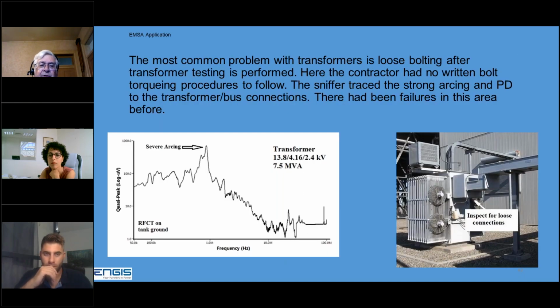The most common problem with transformers is loose bolting after you do a Doble test on the transformer. At this particular site in Wyoming, the contractor had no written bolt torque procedures to follow. The sniffer traced the strong arcing that we saw here, again around 1 megahertz, to the connections for the non-seg bus going into the side of the transformer. This is where the arcing was taking place. And when we told them that, they said, well, we've had failures there before. Well, this basically is because there was no written procedure by the contractor to follow.